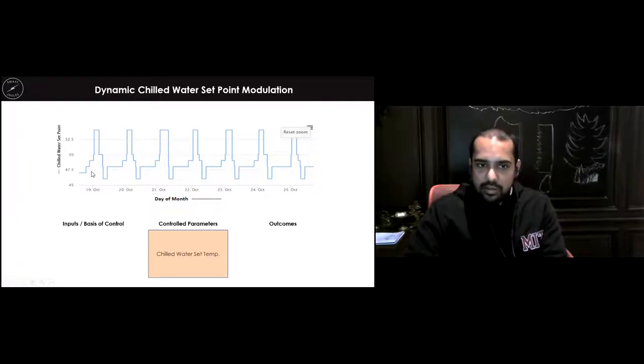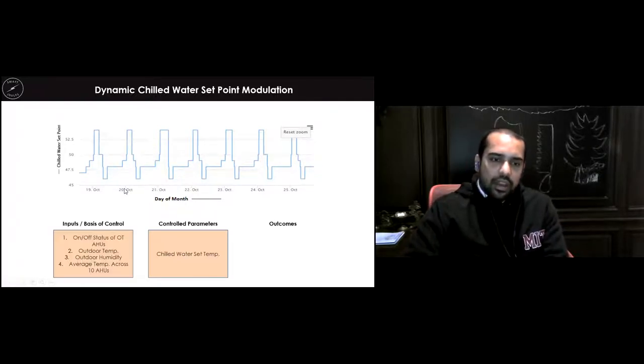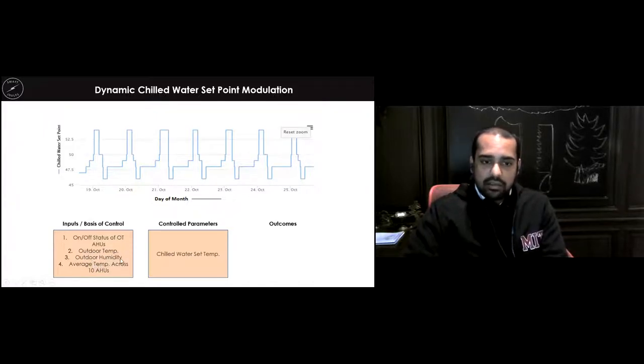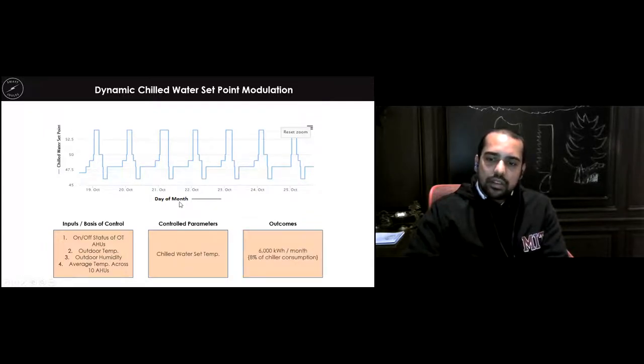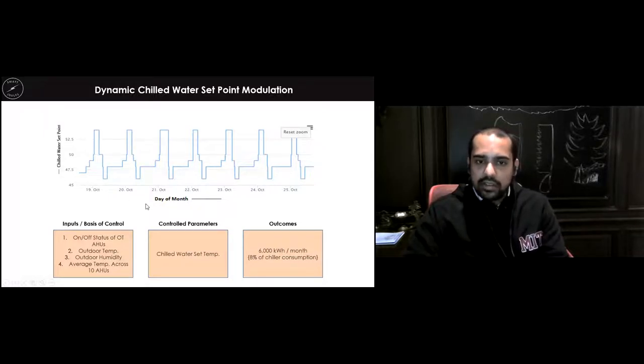So what are the types of inputs that are being taken to control chilled water set point? First, this is for a hospital building. So whether the operation theater is on or not, critical operation theaters, because if they are on, you require a low chilled water set point because the humidity and temperature requirements in the operation theaters are most stringent, and the other areas are not as much. So that is one of the inputs. What is the outdoor temperature, outdoor humidity, and what is the average supply temperature or area temperature across 10 different areas? All these inputs are taken into account, and based on that, you automatically control chilled water set point. In this particular case, about 8% of the chiller consumption is reduced without actually impacting the comfort level at all. In fact, it improves the service level of the air conditioning that you need.